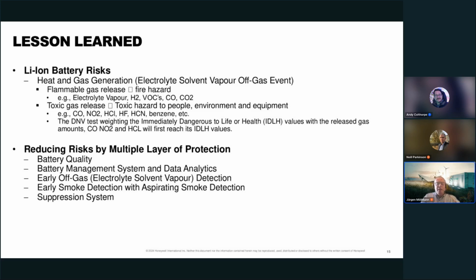Lesson learned quickly: heat and gas generation, the electrolyte solvent vapour off-gas event. During the thermal runaway, we have this flammable gas release, but also toxic gas release. From my point of view, that's a little more difficult and more dangerous because you cannot see it. The fire you can see and everyone will run away. On the toxic side, toxic gas detection, or gas hazard, is more difficult.